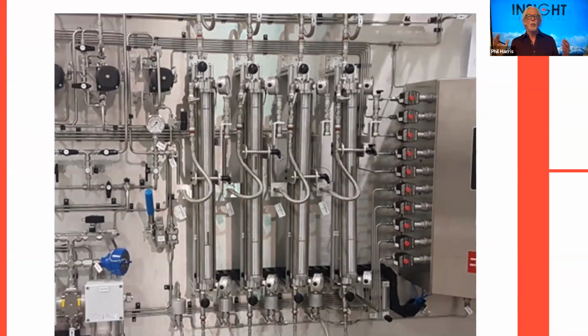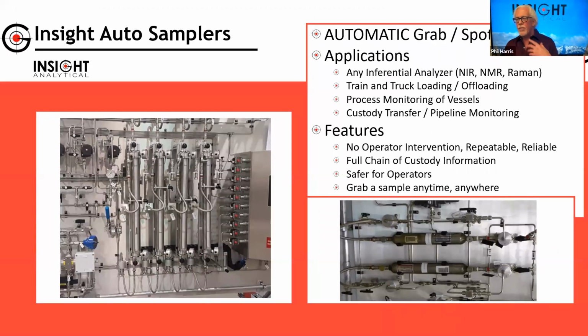We often want to get a sample during a plant upset, but everybody is busy dealing with the upset and nobody can get out there to pull it. So we just trigger the PLC and tell it we want a sample right now. We've done this for floating piston cylinders like I just showed, and the ones over here are what we refer to as glycol displacement cylinders, which can also be used for high volatility products like butanes and pentanes.